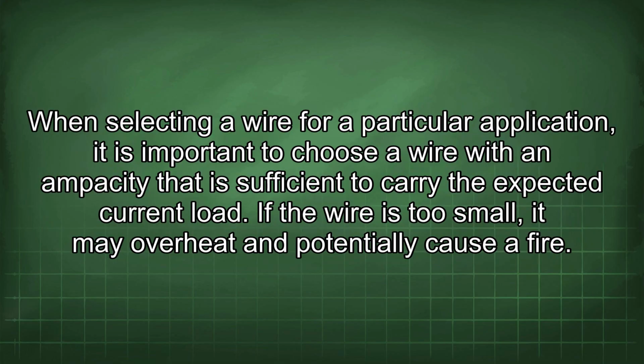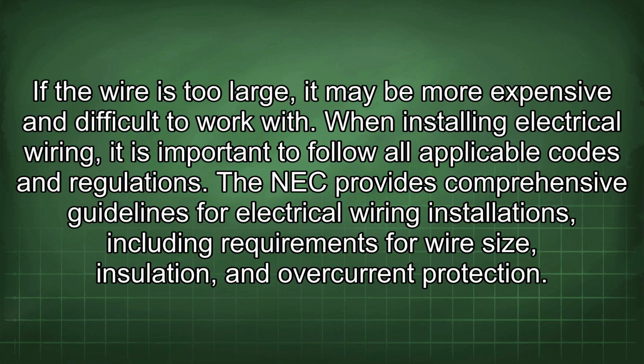When selecting a wire for a particular application, it is important to choose a wire with an ampacity that is sufficient to carry the expected current load. If the wire is too small, it may overheat and potentially cause a fire. If the wire is too large, it may be more expensive and difficult to work with.